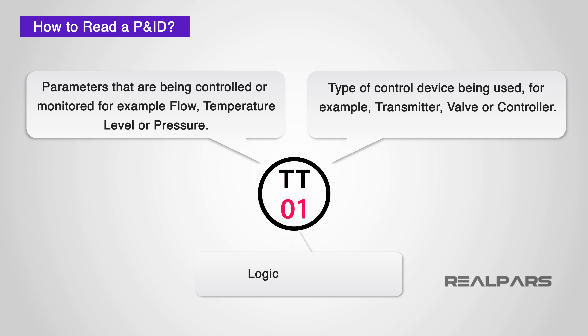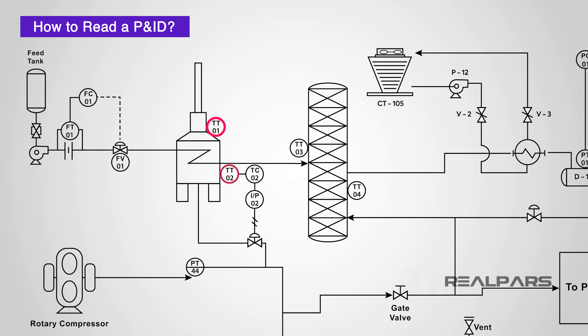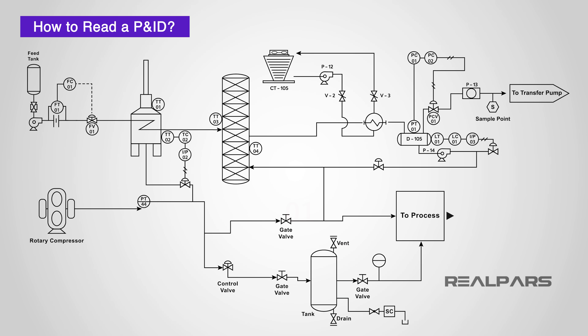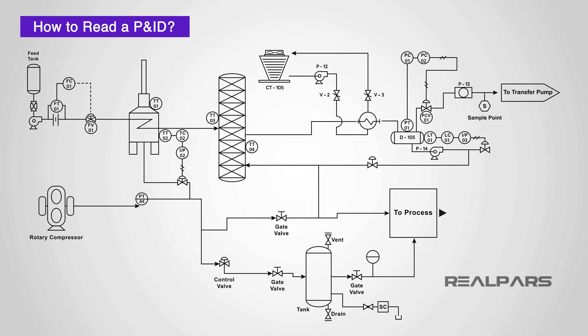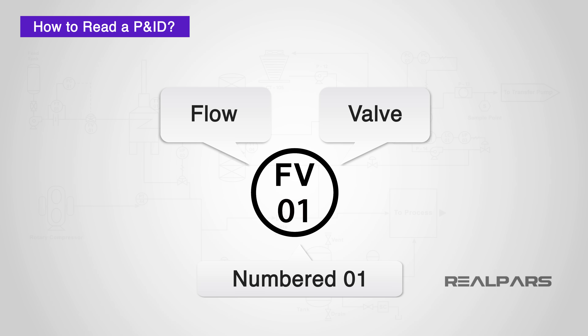The number refers to the logical numerator. For example, we may have a system with four temperature transmitters — it makes sense to identify these as TT01, TT02, TT03, and TT04. Consider an instrument on a P&ID named FV01. Looking up the code, we can tell this is a flow valve numbered 01.